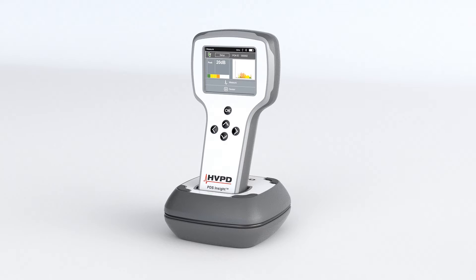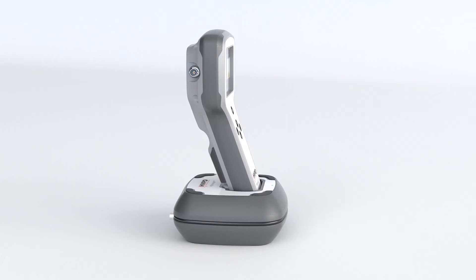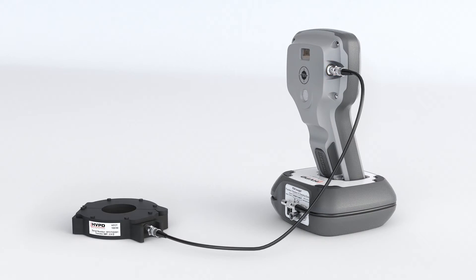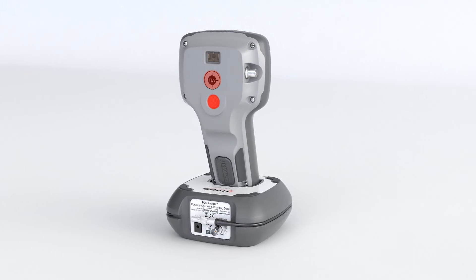The PDS Insight instantly displays test results on its 3.5-inch colour LCD screen. It incorporates three sensors: an external split-core HFCT detects partial discharge in power cables. Integrated TEV and airborne acoustic sensors detect local partial discharge in switchgear and metal-clad plant.